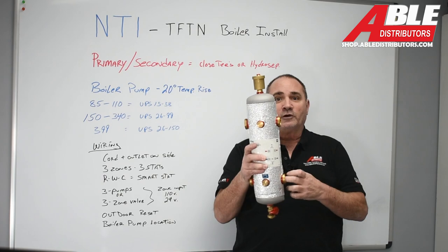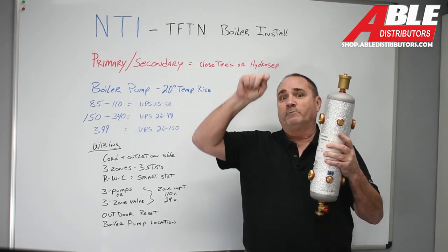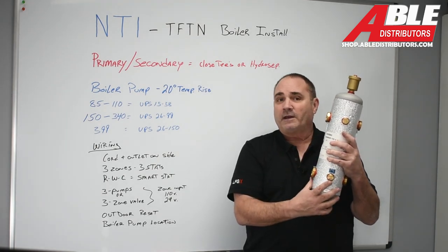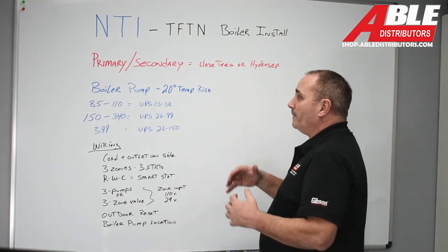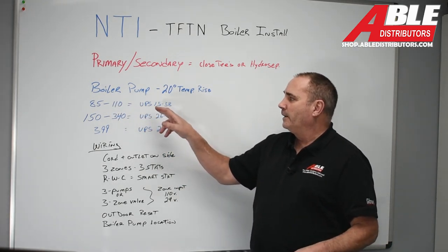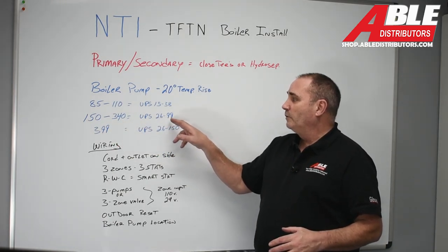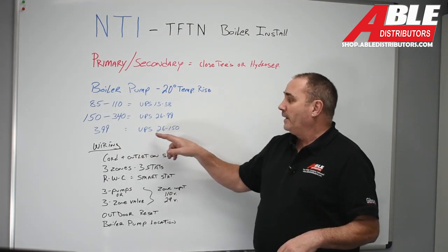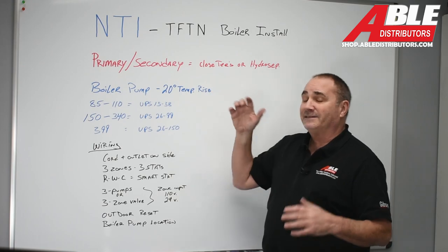With a Hydro-Sep, I'd have a pump on the return pushing into the boiler and out the supply — keep the supply on top. You get an air separator, a spot for a pressure-temperature gauge, and a mag strainer on the return side, plus a drain. For pump sizing on a 20-degree delta T: the 85 through 110 uses a UPS 15-58; the 150 through 340 wants a 26-99; the 399 wants a 26-150. You can't just put a 15-58 on all of them. Primary-secondary is definitely the way to go with this boiler.